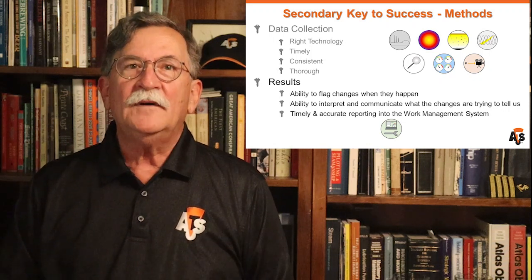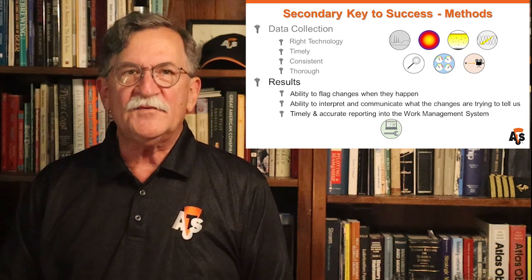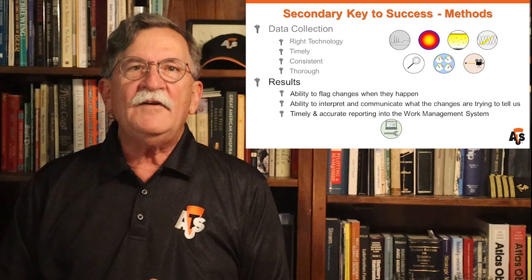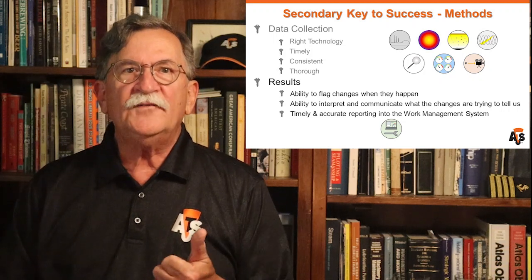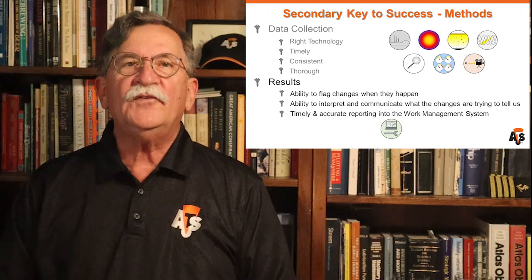The final step is to be sure to enter all the findings and recommendations into the work management system so that the corrective action can be properly prioritized, planned, scheduled, and have the appropriate resources allocated to it. I've seen more cases than I'd care to count where problems were identified, but corrective action wasn't taken in time, and the machine failed, primarily because of a breakdown in the communication handoff. No real surprises there.